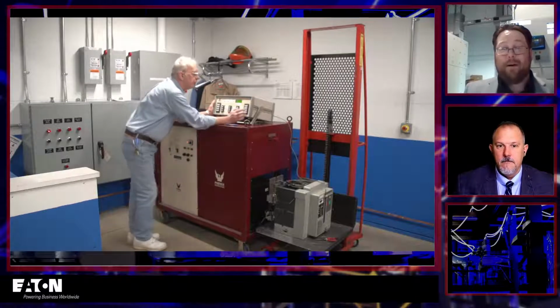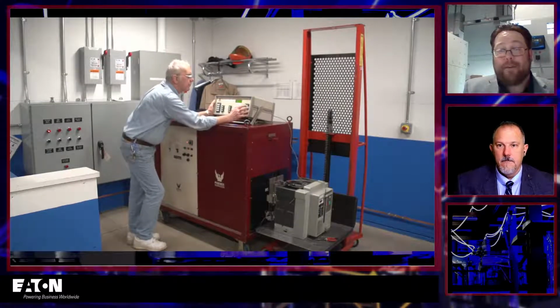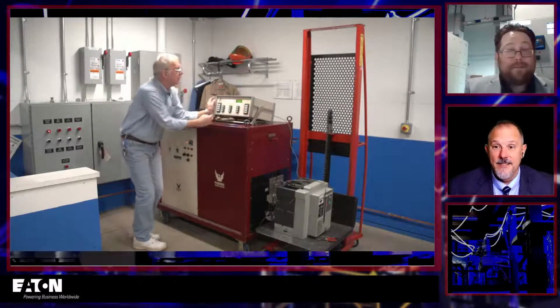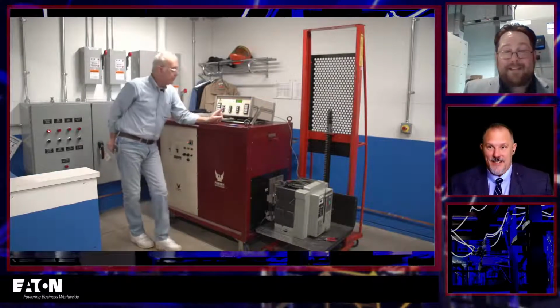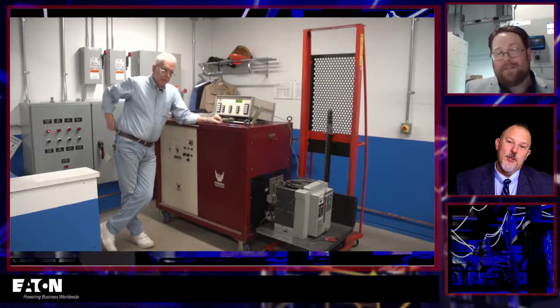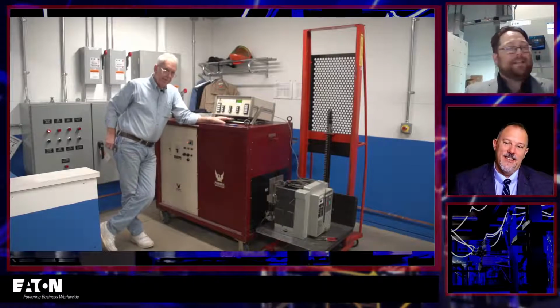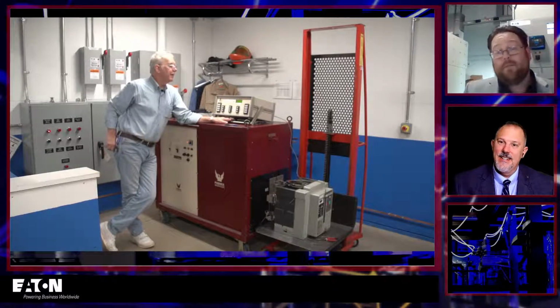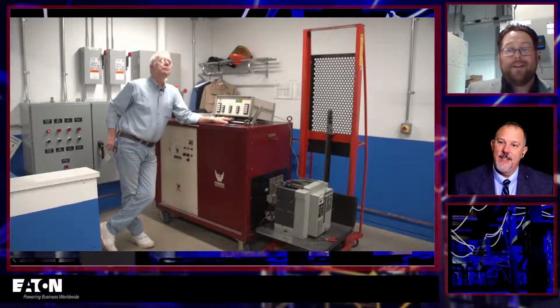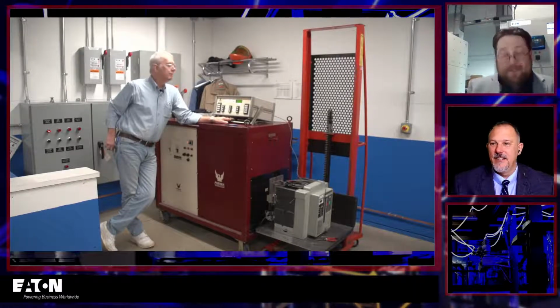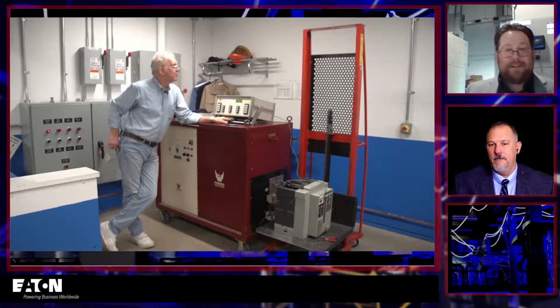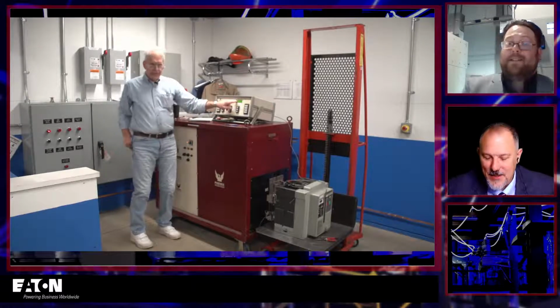And then we didn't even talk about where the test set gets its power from. That's a three-phase test set, so the power coming in could be 208, 480 volts, and it needs a 400 amp service. Now you're at your facility, and you're just building this facility. You don't have utility yet. How do you get the power? Now you're renting a generator to run the test set. Wow, I never thought about that. You're right.